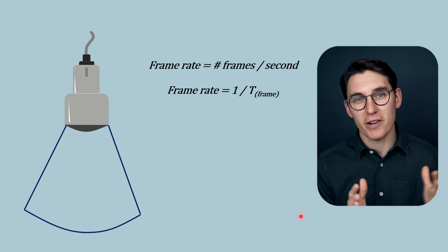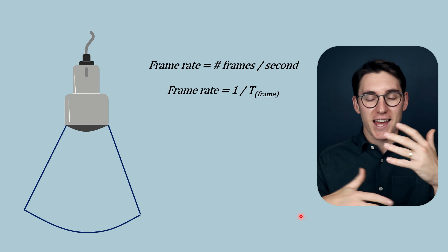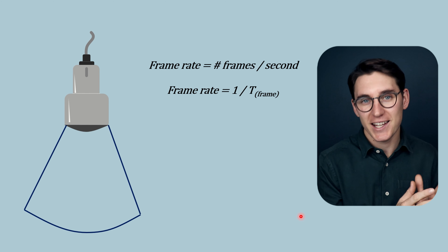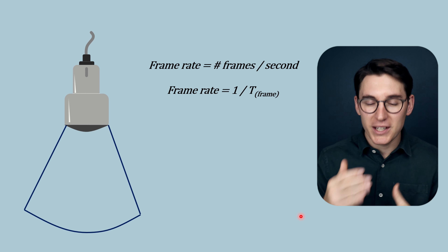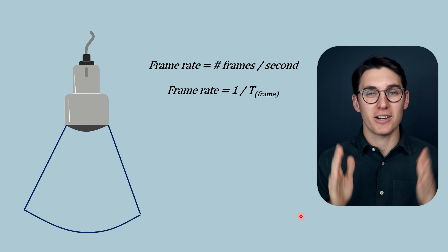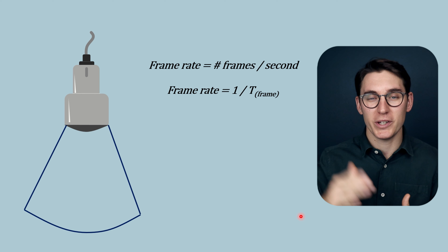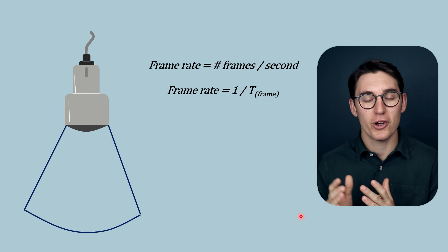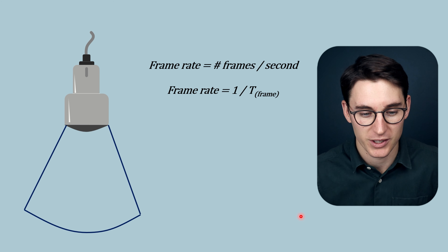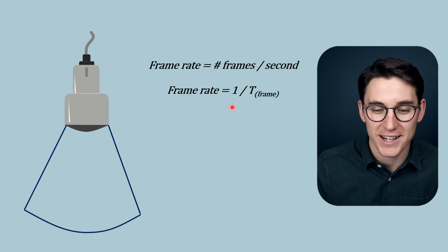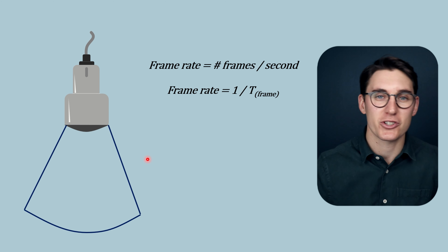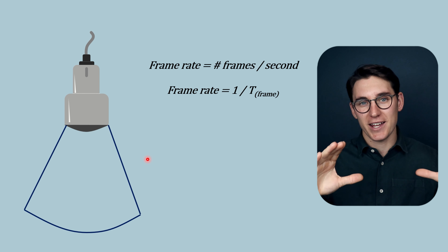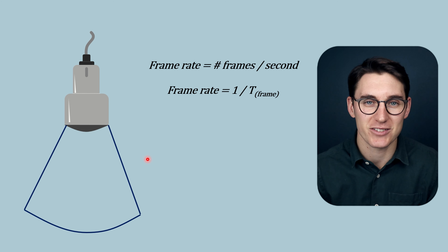In most videos we watch, anything above 24 frames per second is perceived as smooth movement. This concept applies in ultrasound imaging. Our frame rate is synonymous with our temporal resolution — the speed at which we can display frames on our ultrasound image determines how much motion we can detect. The frame rate is determined by the number of frames per second of image acquisition, or equivalently, one second divided by the time it takes to acquire one single frame.